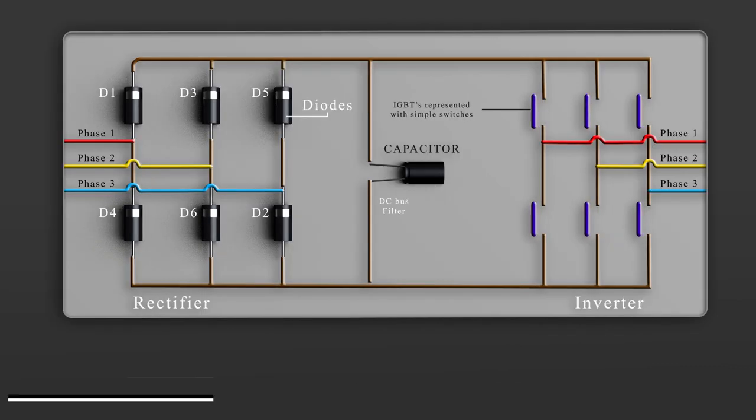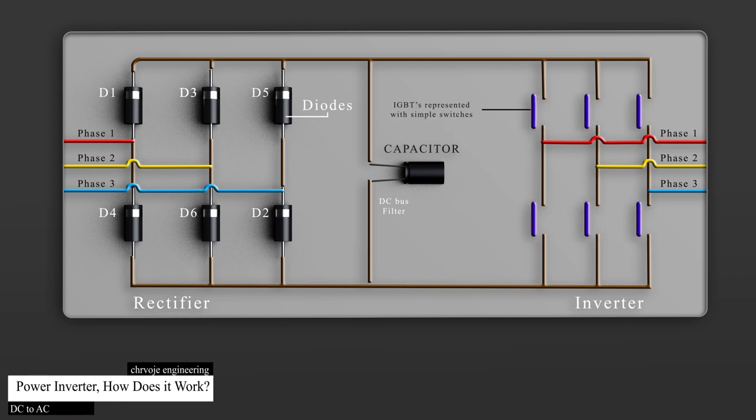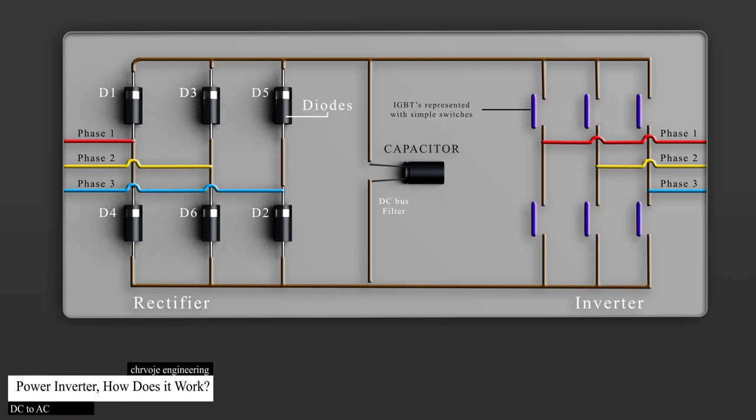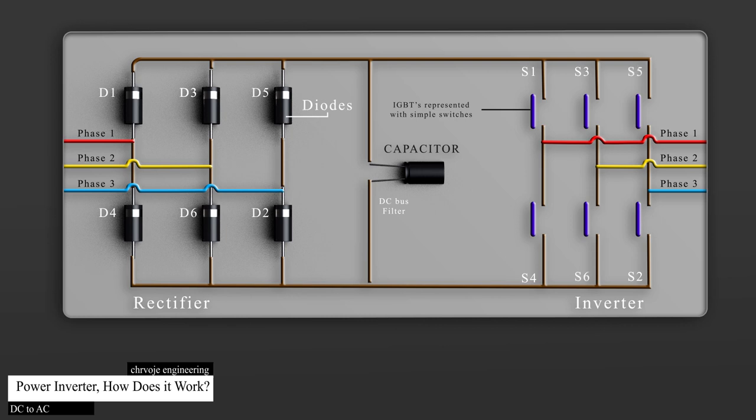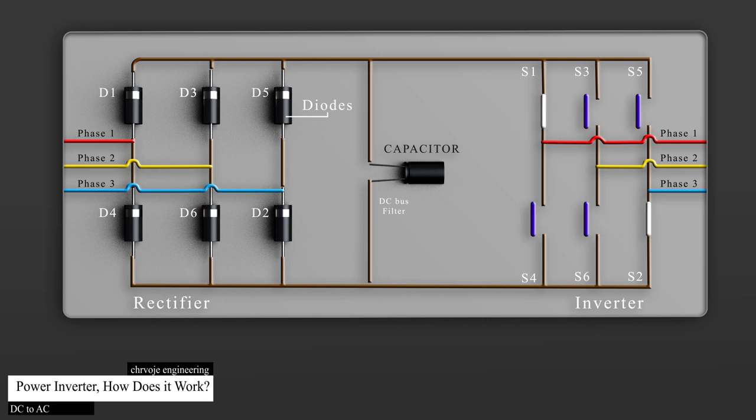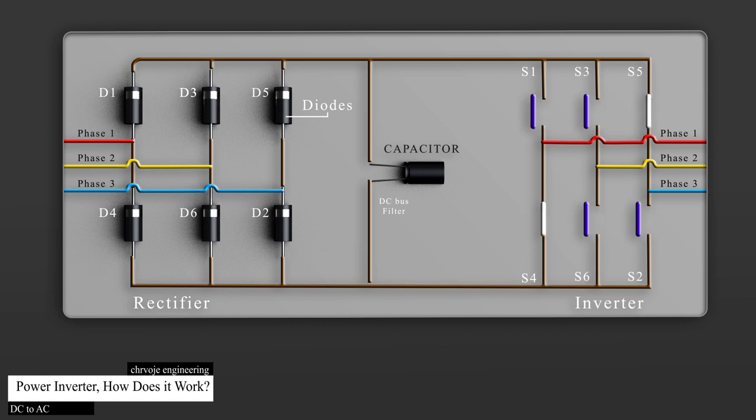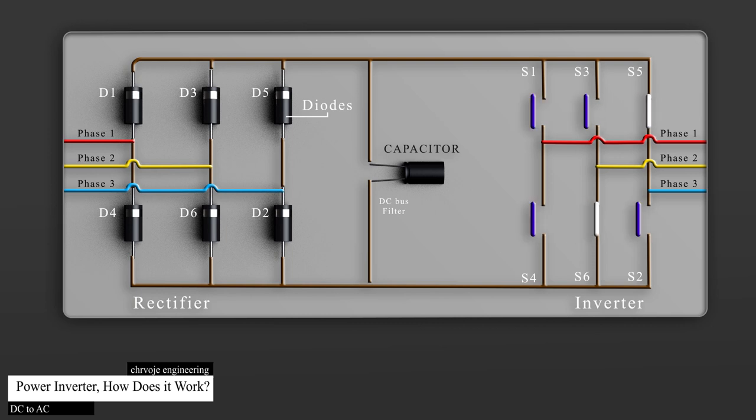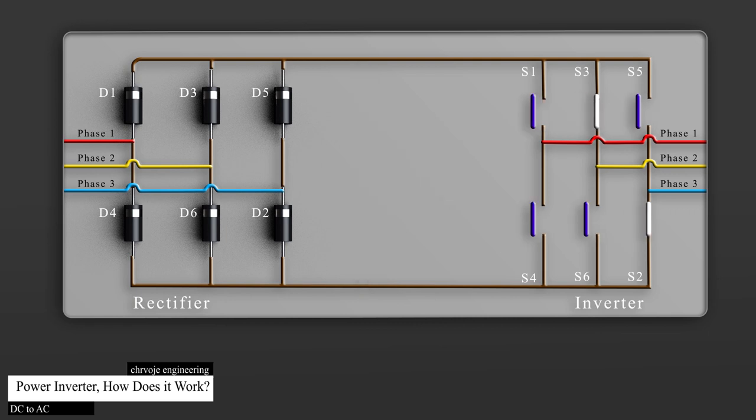To turn the clean DC into three-phase AC, we use a three-phase inverter. Like in single-phase, in three-phase inverter, we use IGBTs. In this case, six IGBTs. We will animate these IGBTs as simple switches for simplicity and mark them as follows. To get our three phases, we need to open and close switches in pairs to direct the flow of the current to our supply and back. Through return pulse, that way the connected motor will experience alternating current. For the three-phase supply, we close and open switches in pairs to simulate the three phases. Let's see how this works.